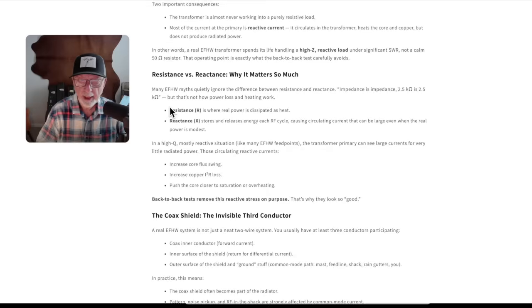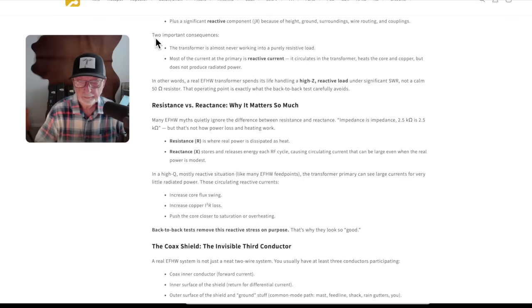Two important consequences: the transformer is almost never working into a purely resistive load. Most of the current at the primary is reactive current. It circulates in the transformer, heats the core and copper, but does not produce radiated power.